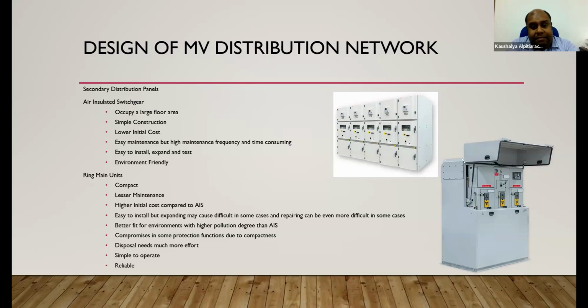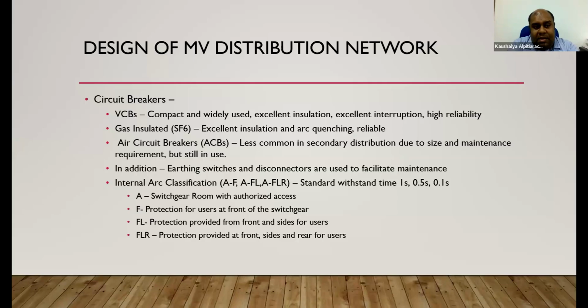Simple to operate and reliable. Circuit breakers, VCBs: compact, widely used, excellent insulation, excellent interruption, highly reliable. That is why it is widely used. Gas insulated SF6: excellent insulation and arc quenching and reliable, but banned in some countries where they follow the Kyoto Protocol.